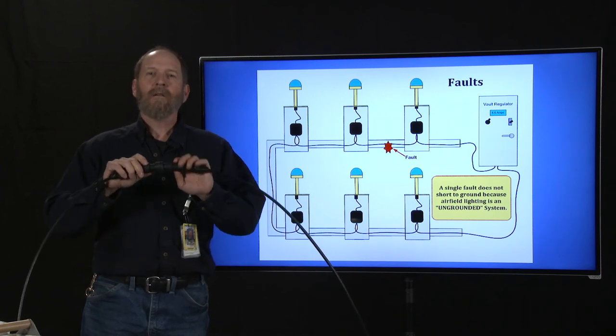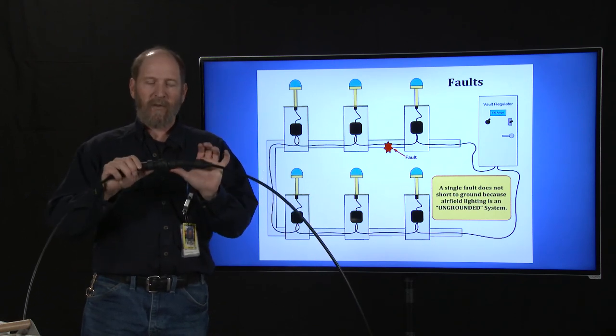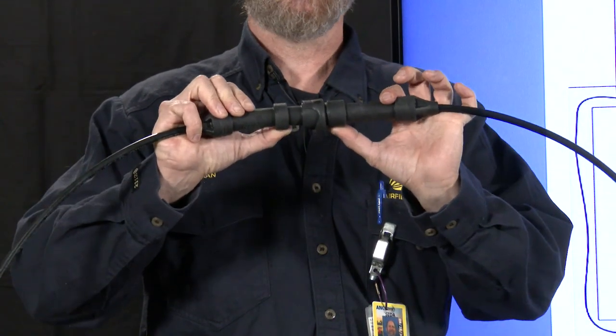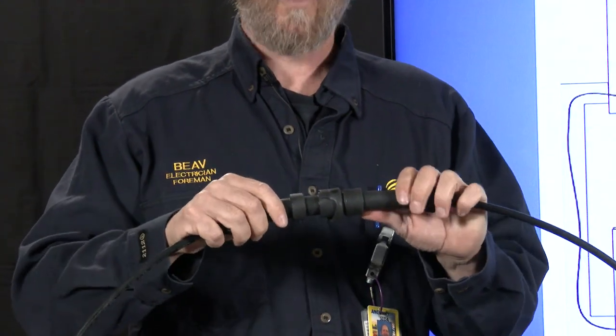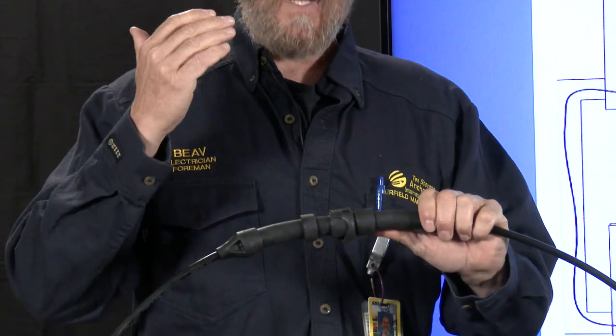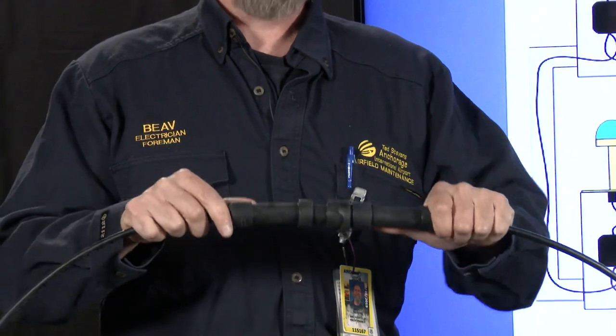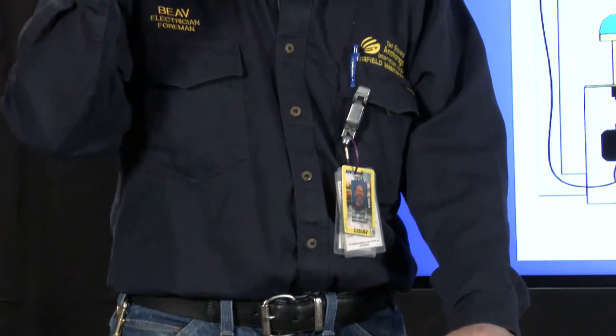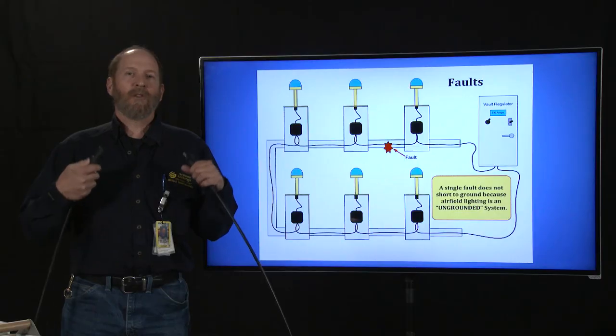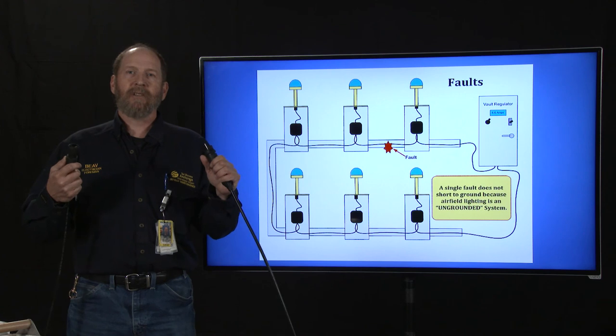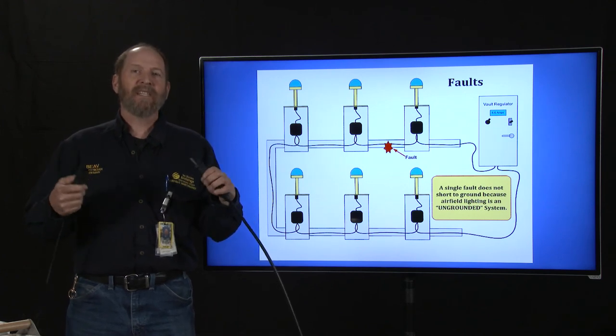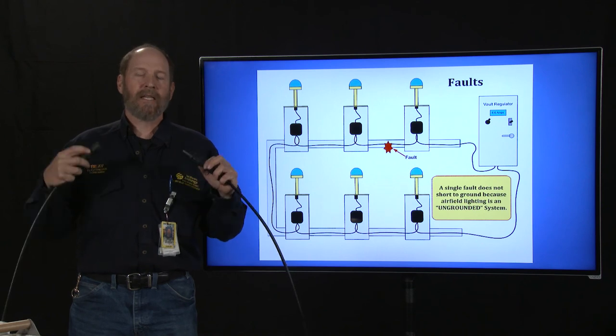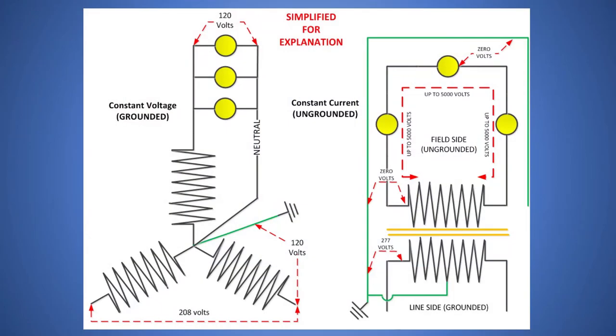Now, if the power company that sends power to your home was to use a connection like this in their 4160 lines, that's typically their transmission lines feeding your transformers, and the lines feeding your homes would probably be about 4160 volts. If they were to feed your house in underground circuits with connections like this, if they took a 4160 line and stuffed it into a metal can with water in it and they turned on the switch, it's going to explode. So why can we get away with using this kind of a connection and they can't? Well, the reason is that our system is ungrounded and their system is grounded. So we'll explain this a little bit more.